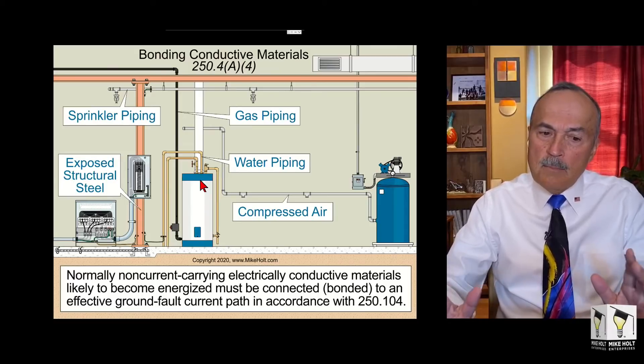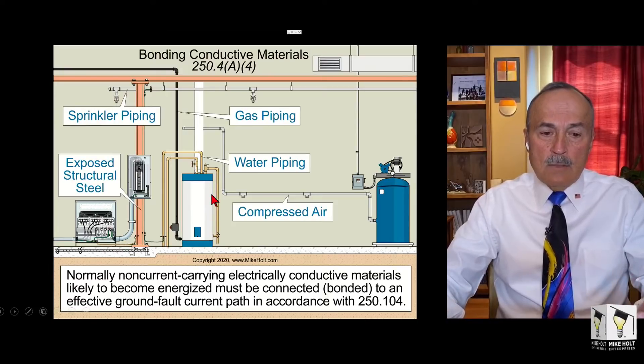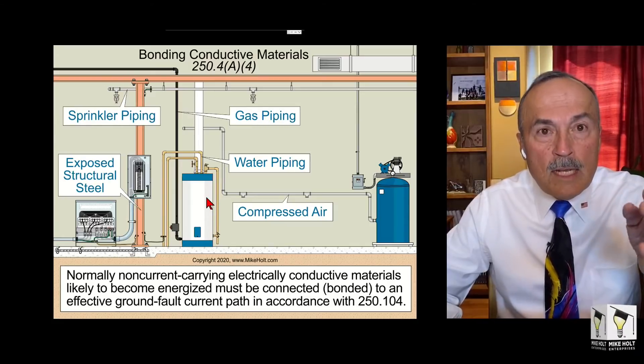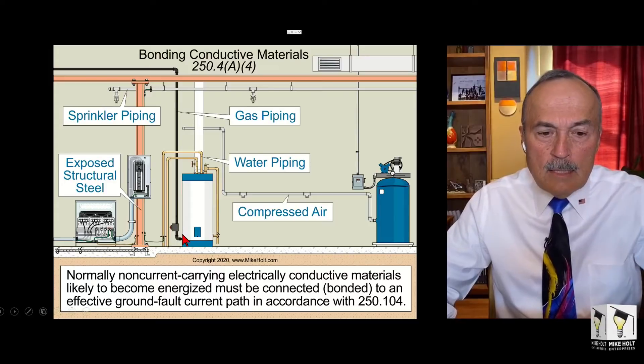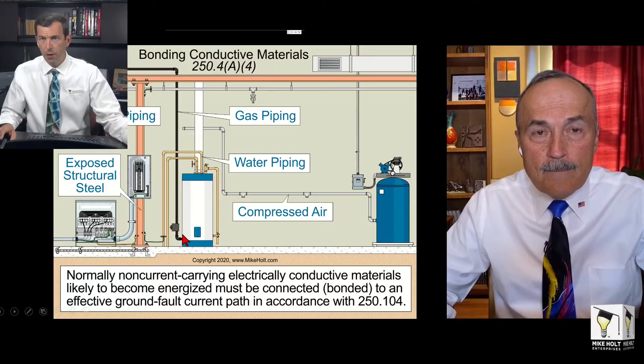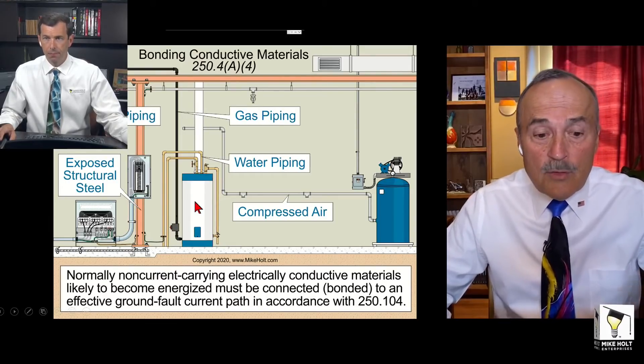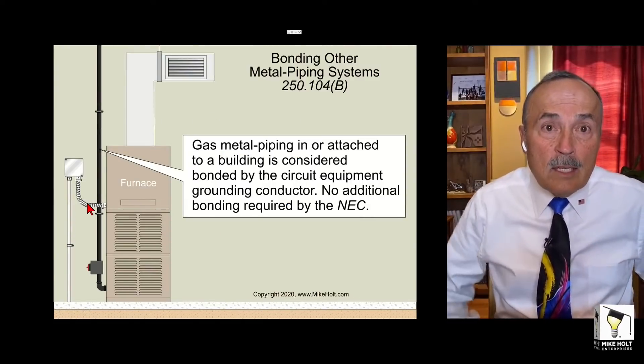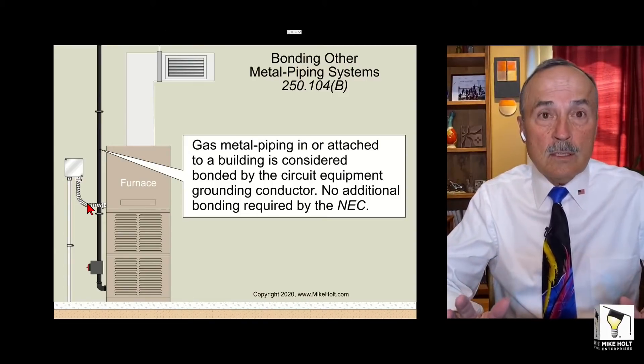If this is a gas water heater, there's no electrical circuit going to it, so this gas pipe is not required to be bonded. If it were an electric water heater, it would be different — but it would automatically be bonded because you have to bring an equipment grounding conductor to the equipment in the first place. Either way, there's nothing additional to do.